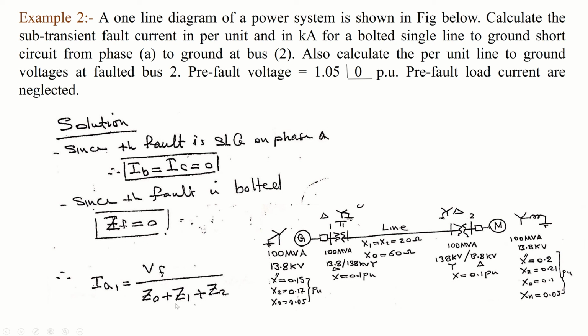So you apply this formula, Vf over Z0 plus Z1 plus Z2. So all this, you have it. This is the generator, this is the transformer, this is the line, this is the second transformer, and this is the motor. So you see the connection. This one is going to be open, and this is to ground, and this is to ground, and this one is open. So it's with this impedance to ground, open with this, for the transformer, for the transmission line, for the transformer, and to ground, and open, and the reactance of the motor.